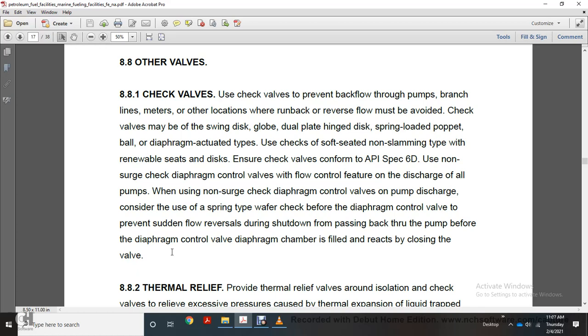Other valves, or check valves. Use check valves to prevent backflow through the pumps. Install them on branch lines with meters, and at locations where reverse flow must be avoided. Check valves that may be used are the swing disc, globe, dual plate hinged disc, spring loaded poppet, and diaphragm actuated types. Use soft seat, non-slamming types with renewable seats and discs. Ensure check valves conform with API spec 6D.